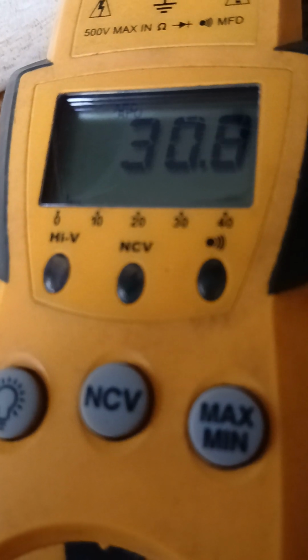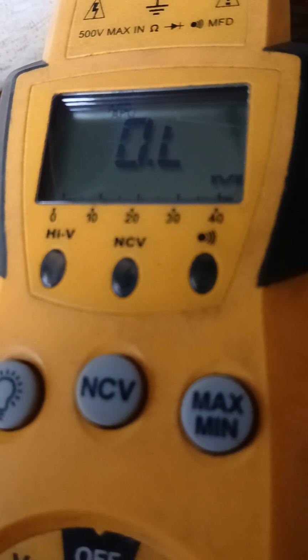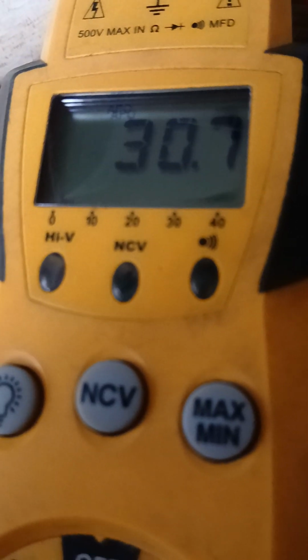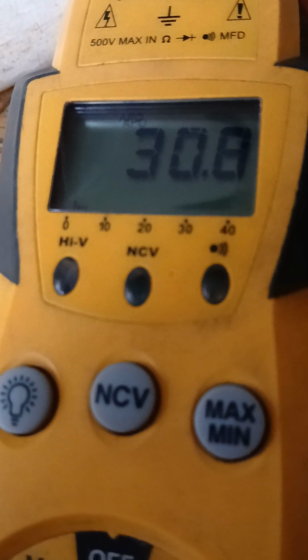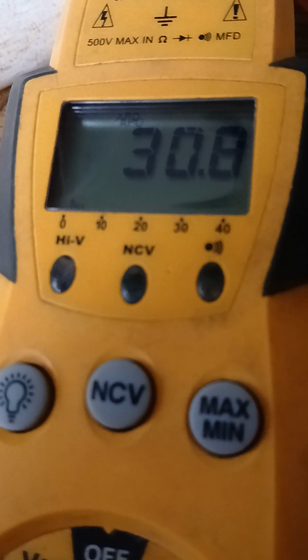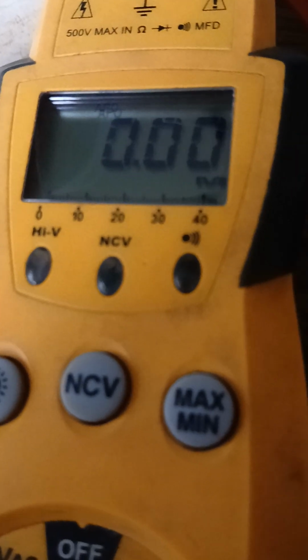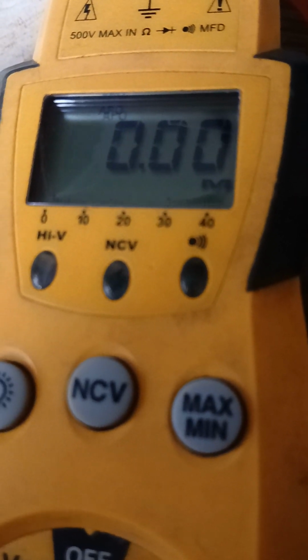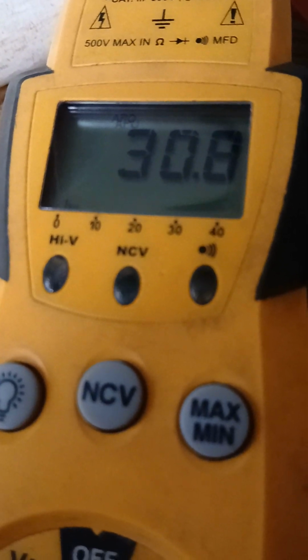Now we can see where the wire is broken. If I go down here, if I'm able to touch this wire - and it's tough again - if I can touch this and make contact, then between the common and the hot, we have around 30.8, or 27, 30.8. So the lead wants to come on and off.